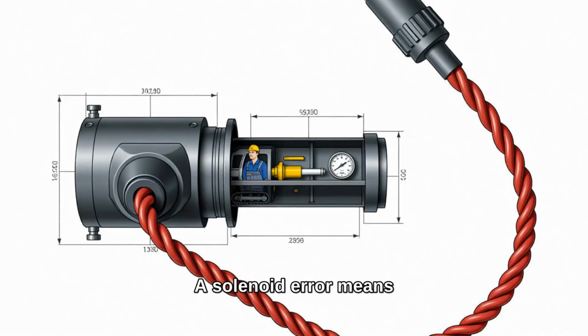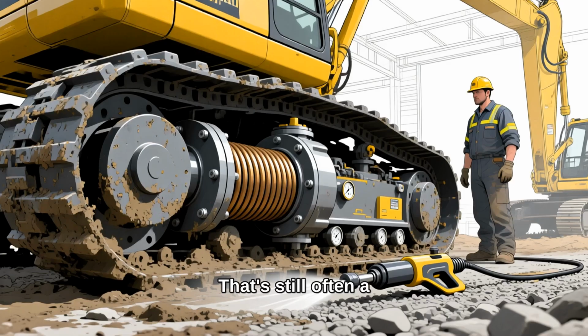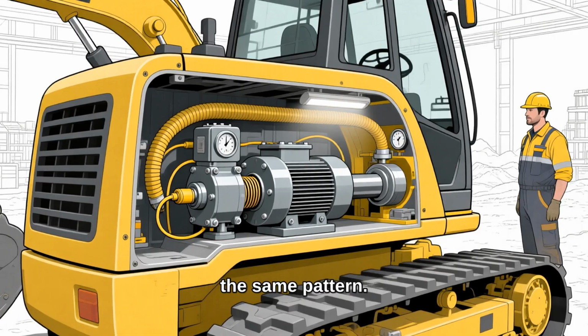A solenoid error means the controller commanded a coil and didn't get back the current it expected. That's still often a connector. Coils sit low on the machine. They get washed. They get hit. The drive side follows the same pattern.